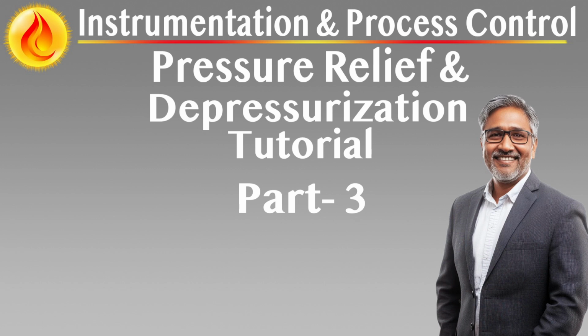Flare system segregation and recovery. In large or complex facilities, segregated flare systems may be used to manage different flow types, reduce costs, or improve combustion performance. Common segregation strategies include high and low pressure separation, especially to accommodate different back pressure tolerances or tip types. Isolation of corrosive or toxic gases, e.g. H2S-rich streams, to avoid widespread contamination and corrosion. Separation of wet and dry streams to prevent hydrate formation or freezing. Flare gas recovery systems may also be implemented to reuse vented hydrocarbons, minimize emissions, and reduce flare load.